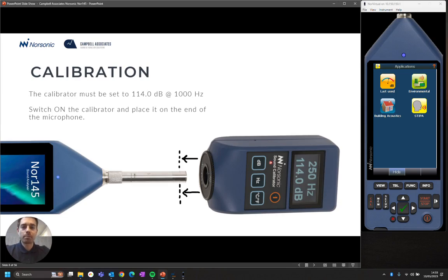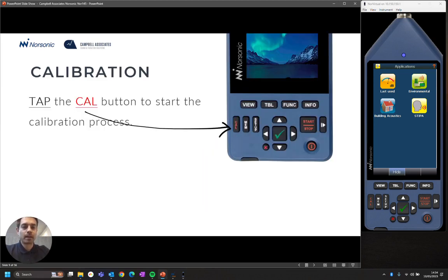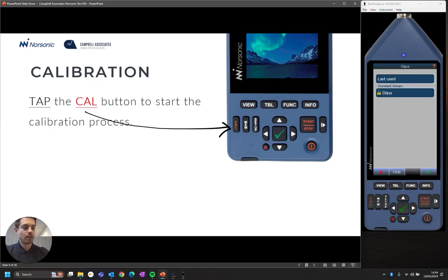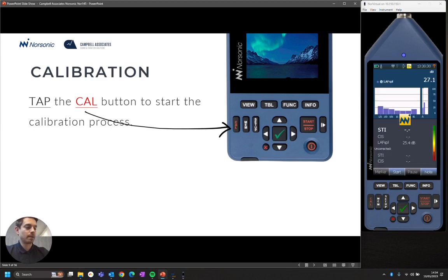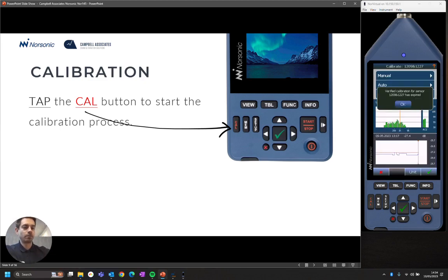So take your calibrator, place this on the end of the microphone. It only goes on 1 centimeter. The calibrator should be set to 114 dB at 1000 Hertz or 1 kilohertz. Turn on the calibrator and then press the cal button on the meter to bring up the calibration screen. So if you've just turned on the meter today, you may need to load in an application first. In that case, tap on the app and tap in the application. Then press the cal button and go through the calibration procedure.